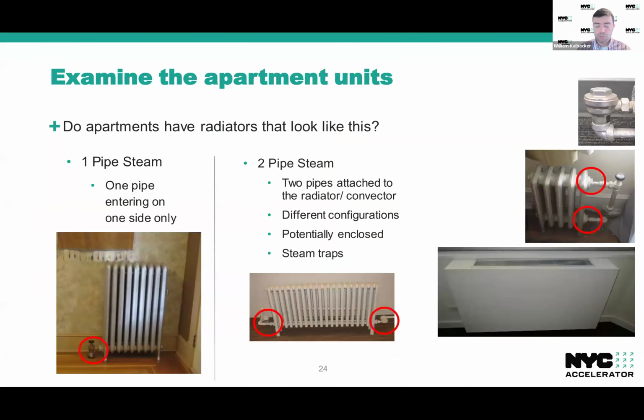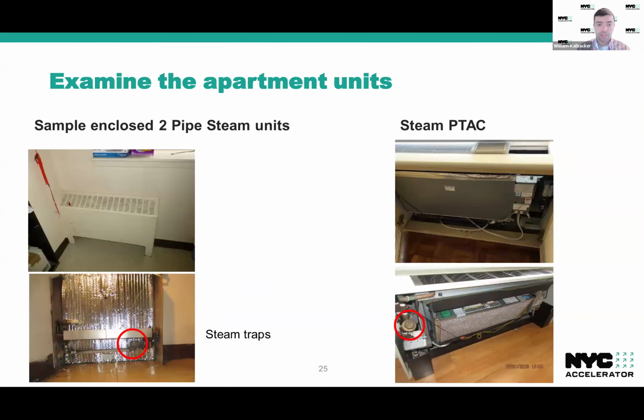In the apartments themselves, there's a wide variety of different types of radiators and convectors and PTACs that might be appropriate for a steam system. Again, one pipe steam, you're going to see just that one pipe coming in and out. You might see a little silver conical shaped air vent as well. For two pipe systems, you're going to see two pipes, one going in, one coming out. You might also see a steam trap, which is a dead giveaway. It's that icon in the upper right here, that little piece of equipment that keeps the steam where it should be. But there are also different types of terminal units that can support steam, like PTACs, recessed radiators, convector cabinets, etc. So there are a wide variety of terminal units here, but a steam trap is a good indicator that you're operating steam.